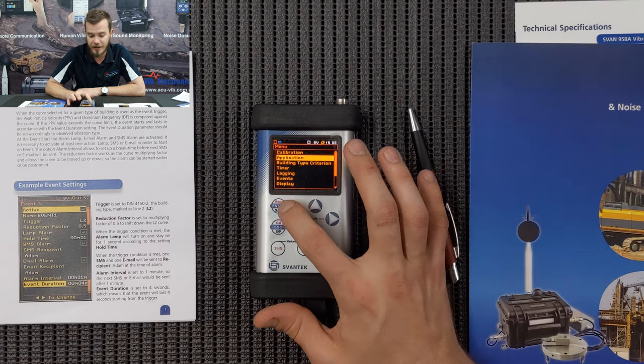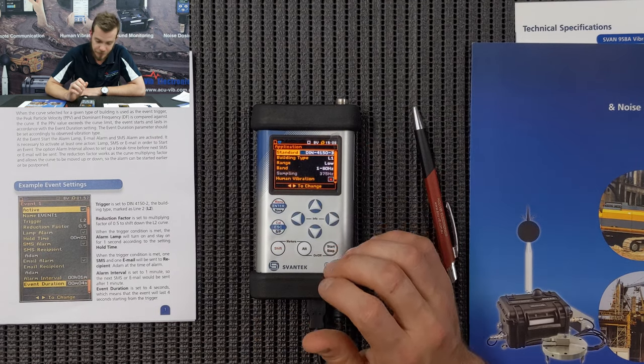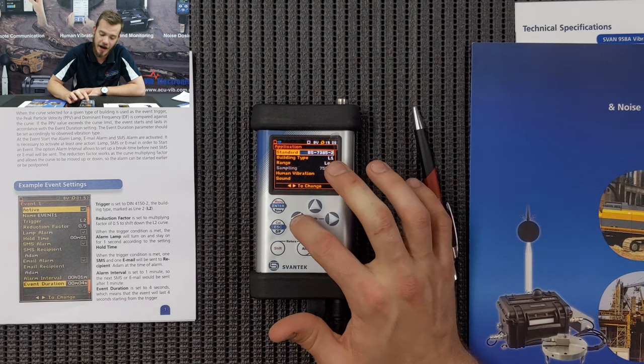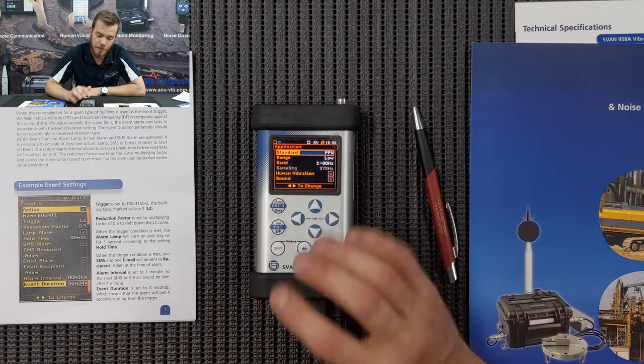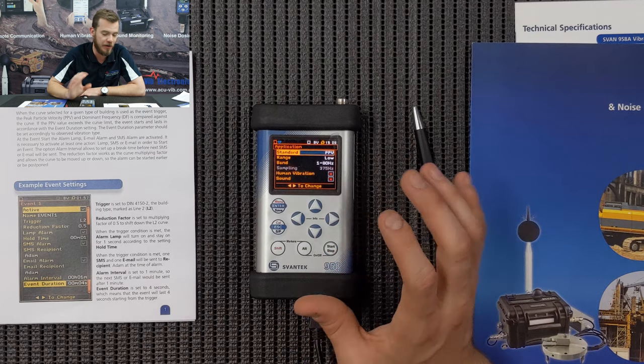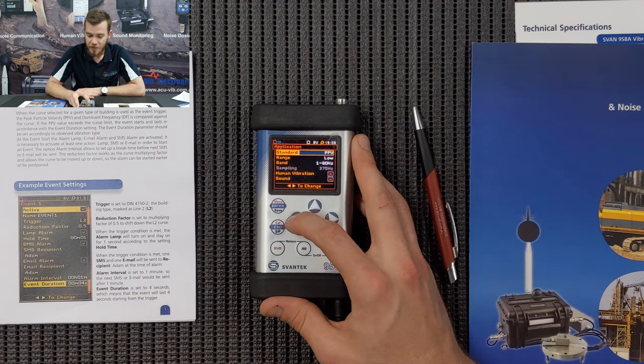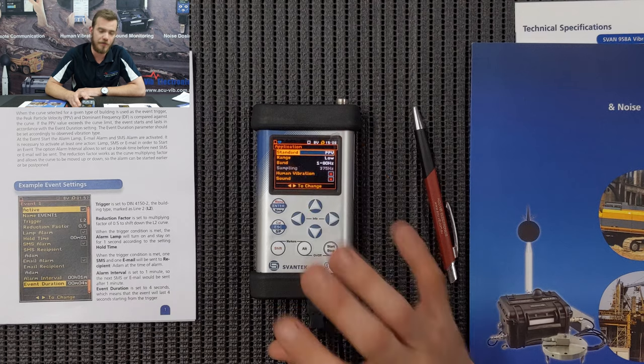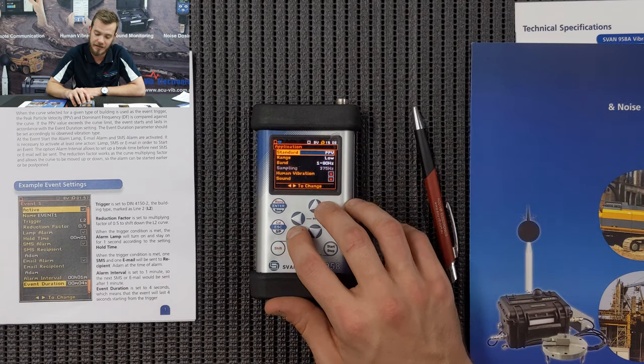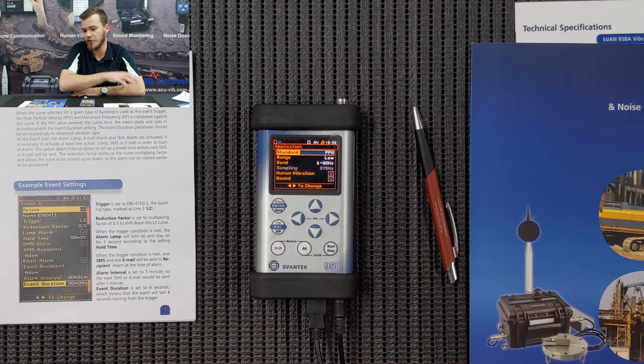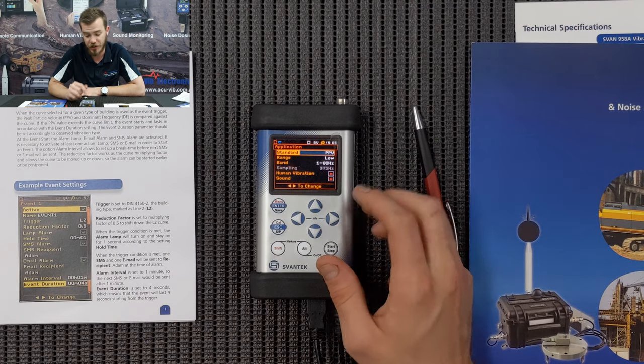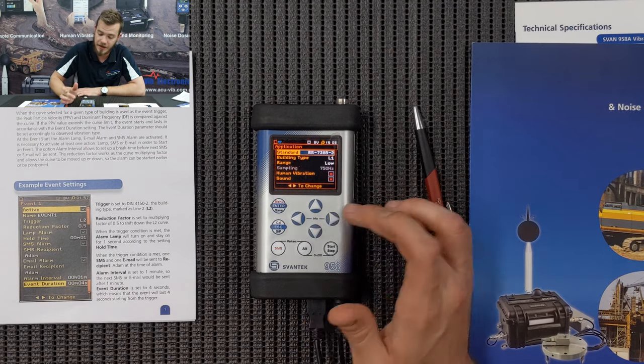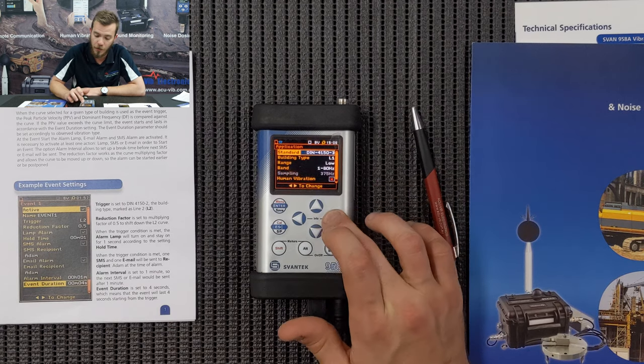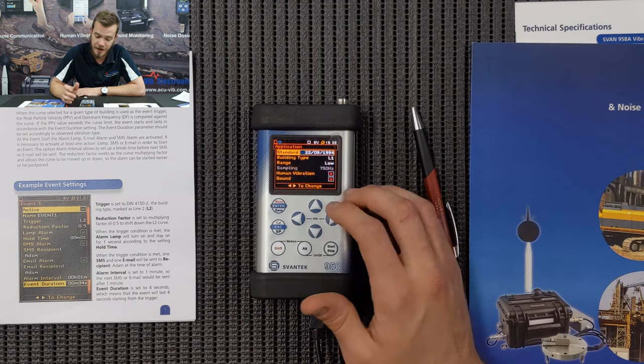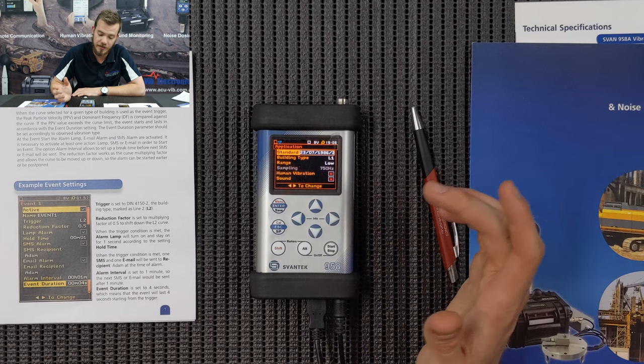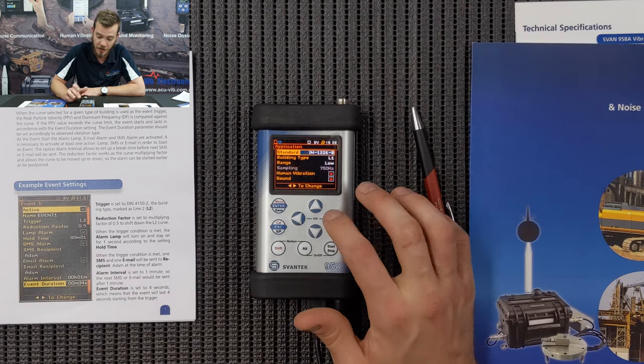So we're going to go down next to the application line. This is basically where you can set up what standard or what parameters you want to be logging your building vibrations for. There's been requests from around the world for people to have their own standards implemented into this firmware. As you know, we've done the two main ones, which is the DIN and also the British. As you can see, there's PPV here, there's the British, there's the DIN 4150, there's KFB Max. There's a number of different standards for different countries. Some of these are in Poland and around the world.